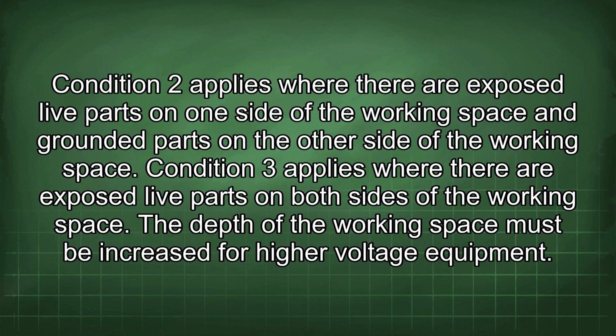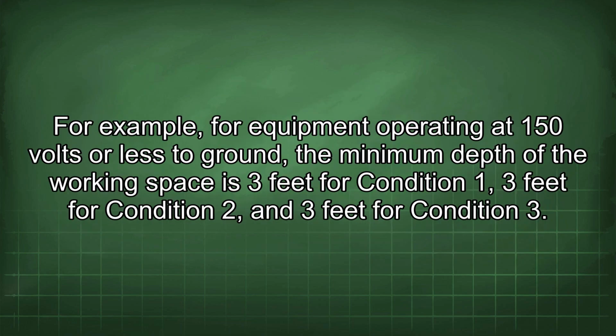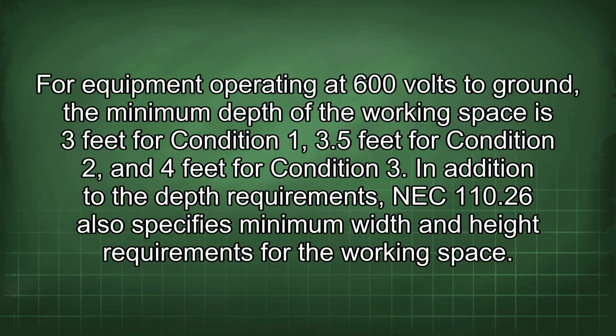The depth of the working space must be increased for higher voltage equipment. For example, for equipment operating at 150 volts or less to ground, the minimum depth of the working space is 3 feet for condition 1, 3 feet for condition 2, and 3 feet for condition 3. For equipment operating at 600 volts to ground, the minimum depth of the working space is 3 feet for condition 1, 3.5 feet for condition 2, and 4 feet for condition 3.